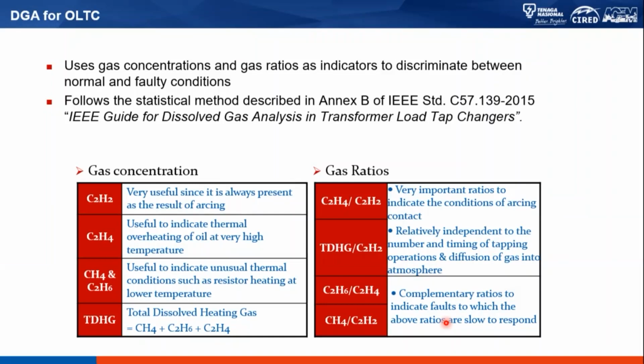In 2010, IEEE released a standard called C57.139, and in 2015 it was revised with a second version, but more or less the content or principle is the same. Some information has been added; for example, in the annex of this guideline, Duval's triangle for OLTC has also been incorporated as part of the standard.